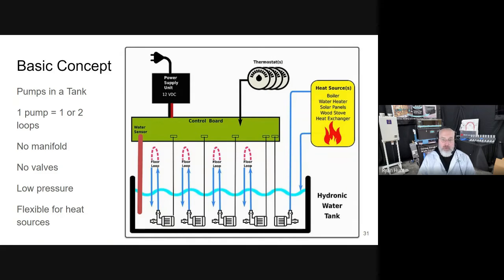We've got a handful of pumps sitting in that water. One pump in the corner sends the water up through a heat source, a boiler or water heater, and that returns the hot water into the tank. And then each of these little pumps sends that water out to the loops in the floor. Each pump connects to one or two loops only. So I'll show you how that works out in real life in a moment.